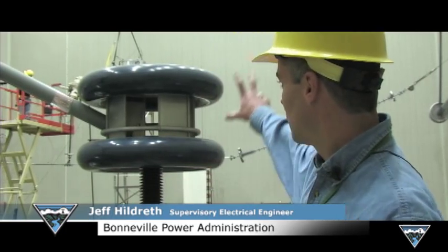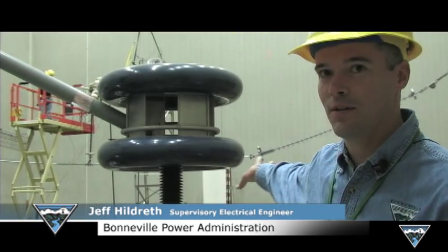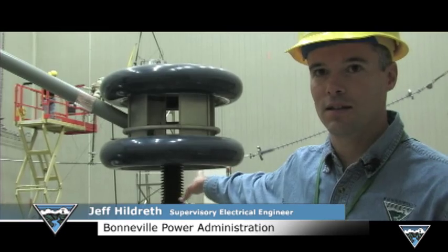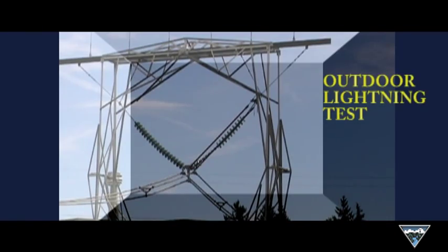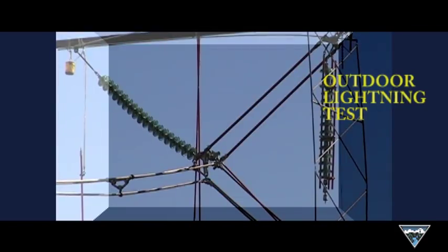And then the other type of test that we do is the impulse generator, which is behind a cloth over there. We're protecting it because of the testing that we're doing today. But with that, we can produce lightning here in the building. That models when lightning strikes our transmission lines. We want to make sure that they can withstand that and all the equipment associated with it can withstand the lightning strike.